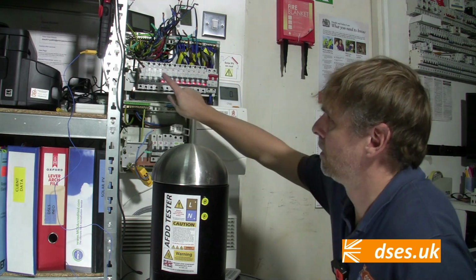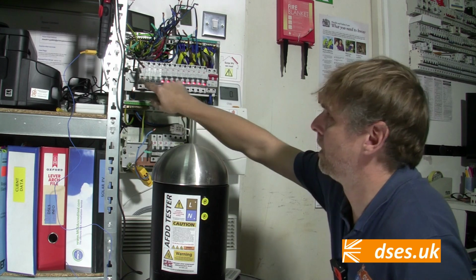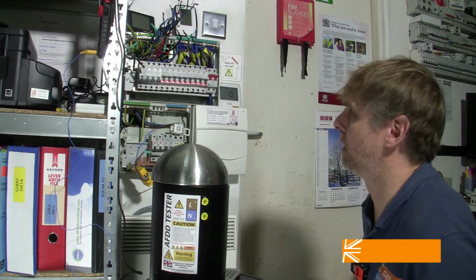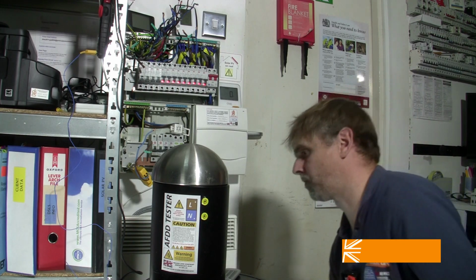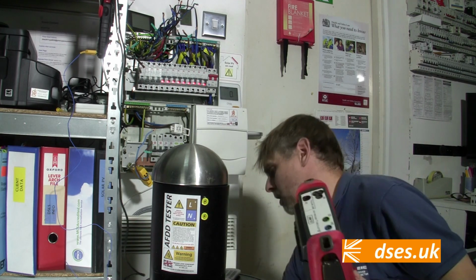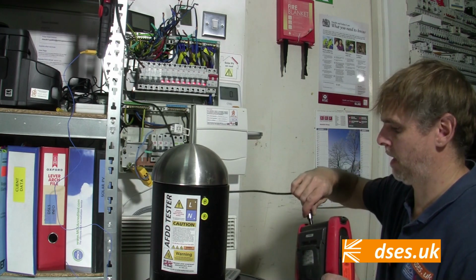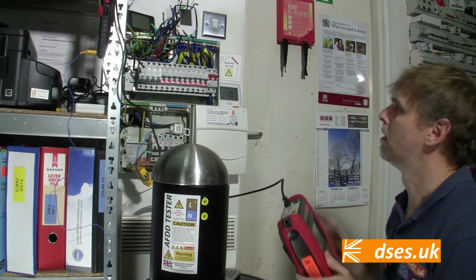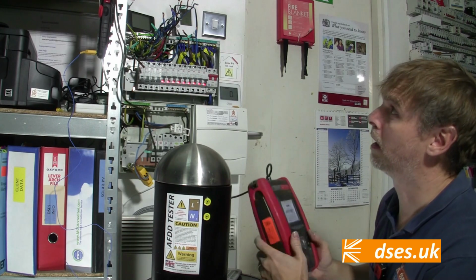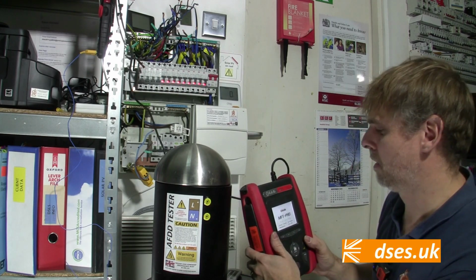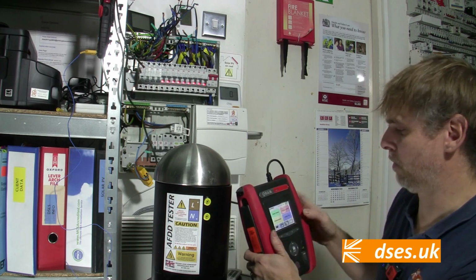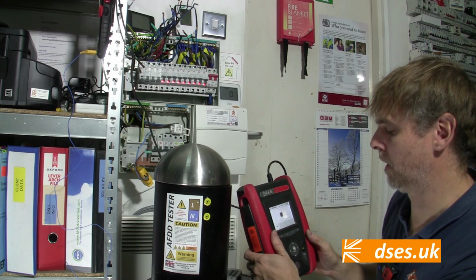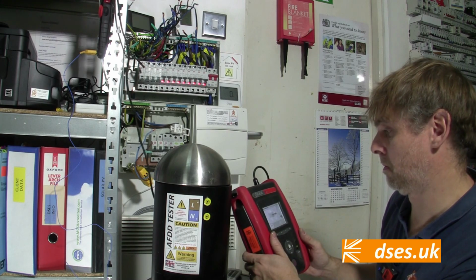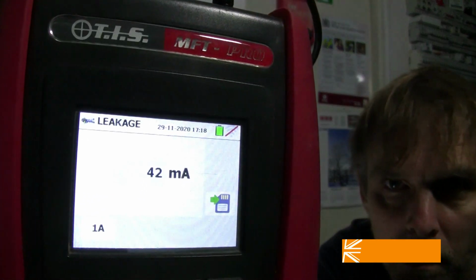There's our 9 AFDDs all illuminated. These next 3 are RCBOs, and you've got a breaker at the end there. Nothing connected. We've only got the AFDDs on at present. I've got my clamp for my TIS MFT Pro around the incoming tail, and I'm going to use the earth leakage function on here to see what sort of current is being drawn. At present, I don't know if you can see that, 42 milliamps.